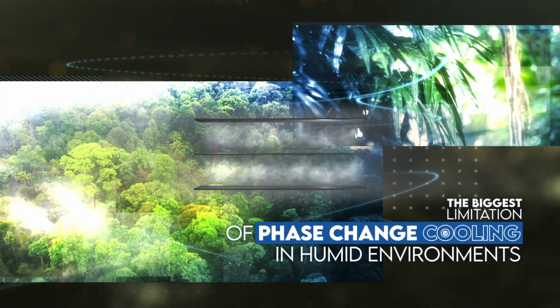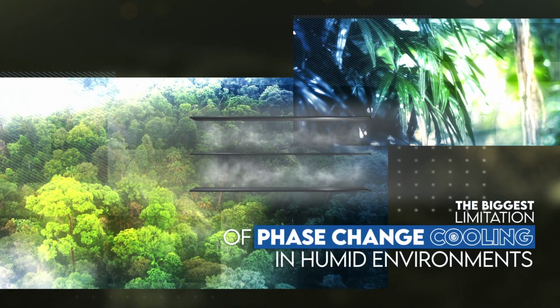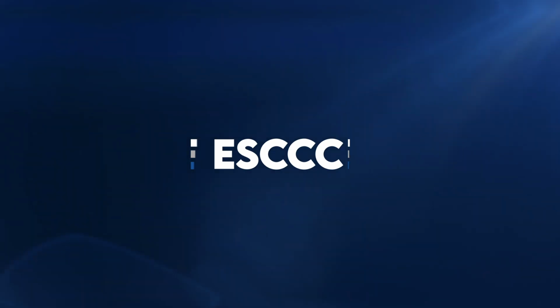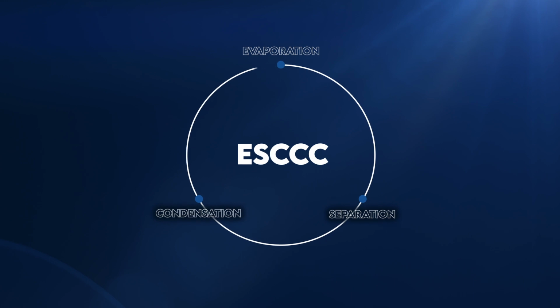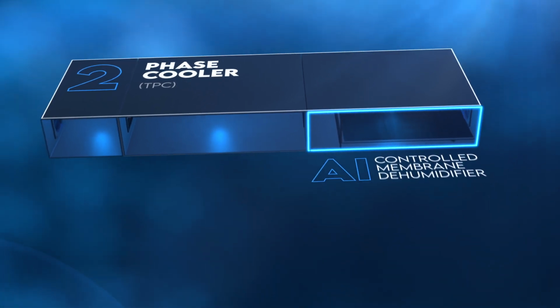The major problem with effective utilization of the phase change process is the humidity of the outdoor air. When the air is humid, the water does not evaporate effectively because the outdoor air is saturated. This was a serious limitation until now. Baryon's revolutionary ESCCC process overcomes these barriers. The evaporation, separation, condensation closed cycle technology, or ESCCC, is realized by a unit made of two elements: a two-phase cooler, or TPC, and a proprietary AI-controlled membrane dehumidifier.